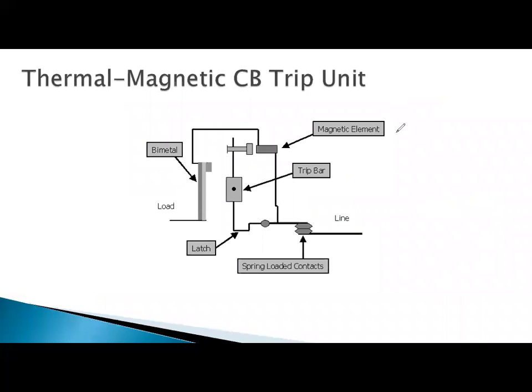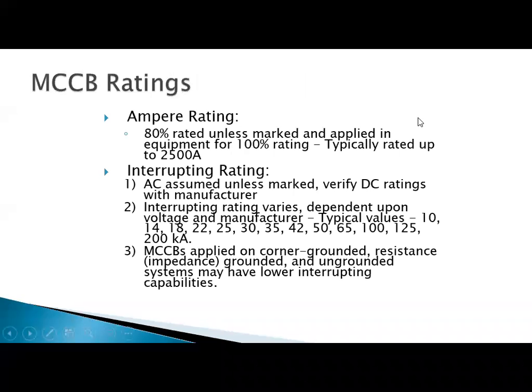But here we can see all the different parts. So our contact, we can manually close these contacts by just reworking our switch. These contacts automatically are going to open on overloads by the bimetallic strip, or they're going to open with the magnetic coil because of short circuit or ground fault. So that's basically how a circuit breaker works. But remember, there are some National Electrical Code considerations that we have to look at. Our normal circuit breakers are rated to operate at 80% of the load. So, for instance, if I have a 20 amp circuit breaker, it can continuously carry 16 amps with no issues.